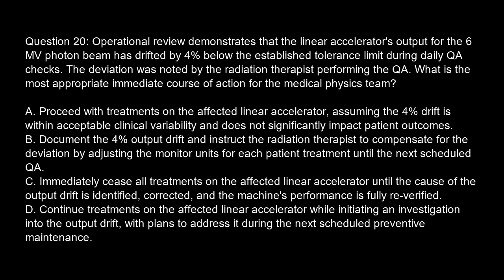Option A. Proceed with treatments on the affected linear accelerator, assuming the 4% drift is within acceptable clinical variability and does not significantly impact patient outcomes. Option B. Document the 4% output drift and instruct the radiation therapist to compensate for the deviation by adjusting the monitor units for each patient treatment until the next scheduled QA.